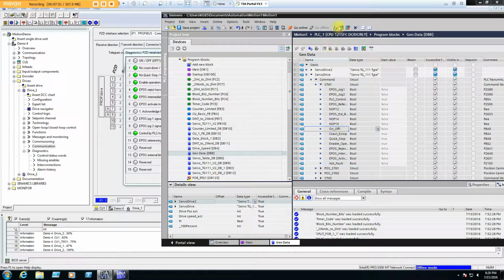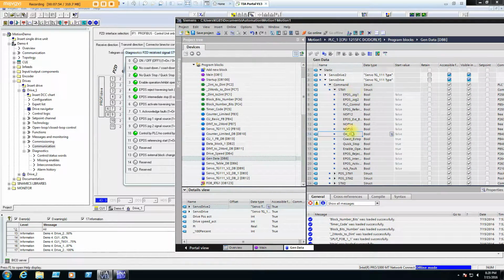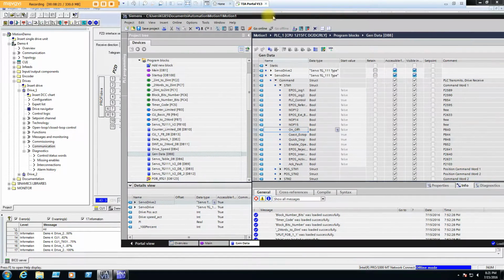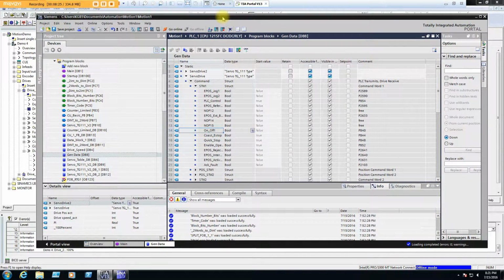Sometimes if I'm dealing with trying to transmit data to a device that I don't know which way it is, I will actually just have a word and I will set the first bit. And then I'll look into the device I'm sending it to and see, does it show up in the zero up here, or does it show up here? If it shows up the opposite, I know that I have to use the command in the PLC to take a word and swap the bytes before I transmit it. I use the word the way I normally use it in my PLC, and then when I transmit it, I'll swap the bytes right before I transmit them.